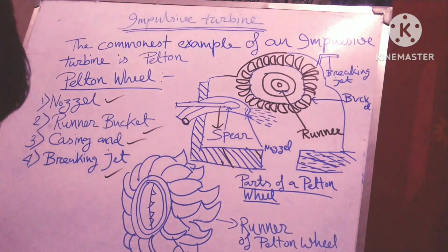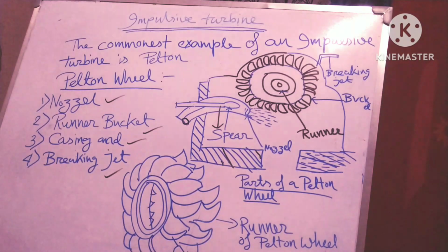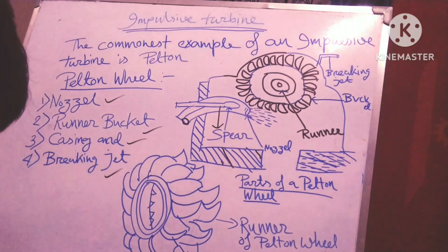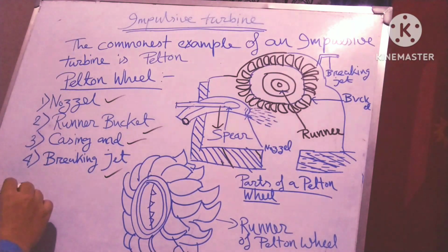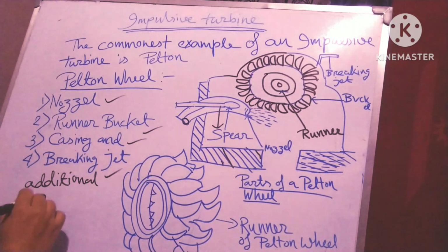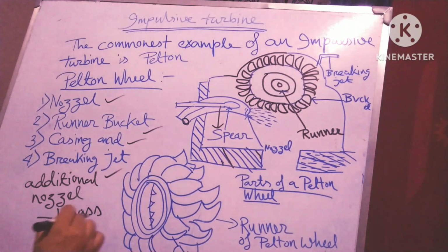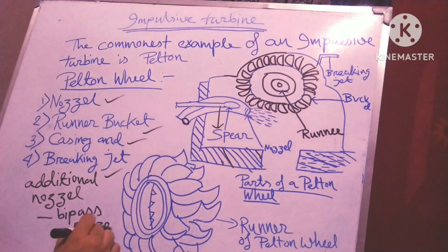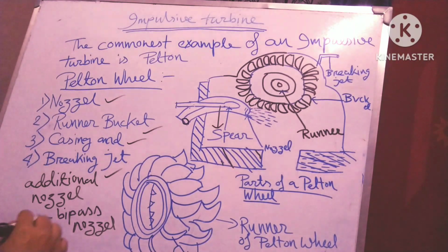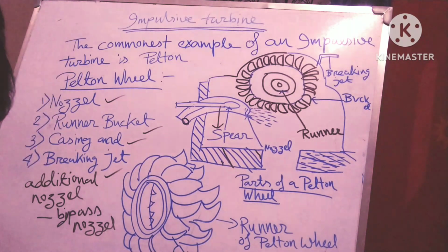In order to avoid such a mishap, an additional nozzle known as a bypass nozzle is provided, through which the water can pass without striking the buckets.